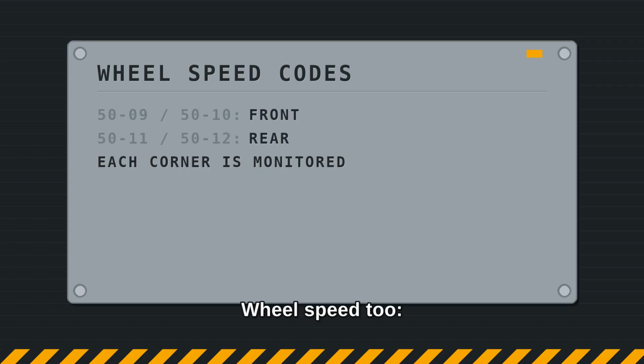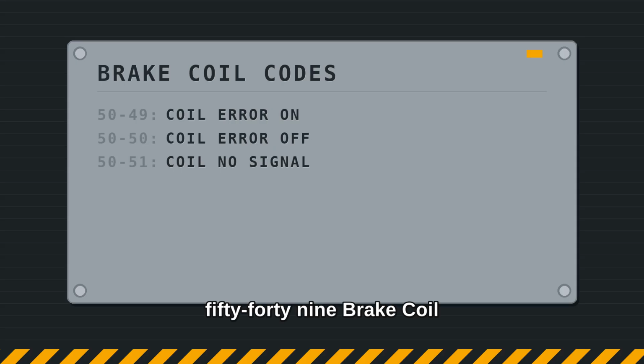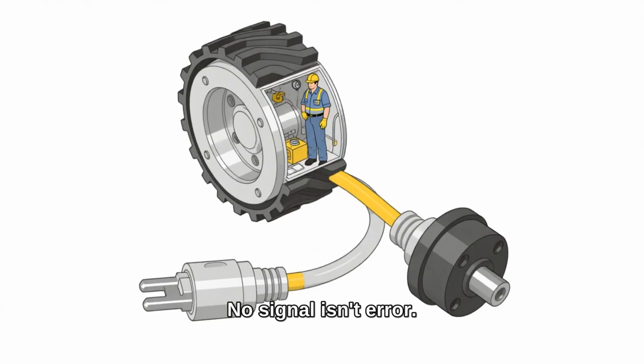Don't assume. Wheel speed too: 50-09 and 50-10 front, 5011 and 5012 rear. Named, specific, checkable. Then the brake circuit. 5049 brake coil, error, ON. 50-50 brake coil, error, OFF. 50-51 brake coil, no signal. No signal isn't error. One means the machine heard something wrong. The other means it heard nothing.